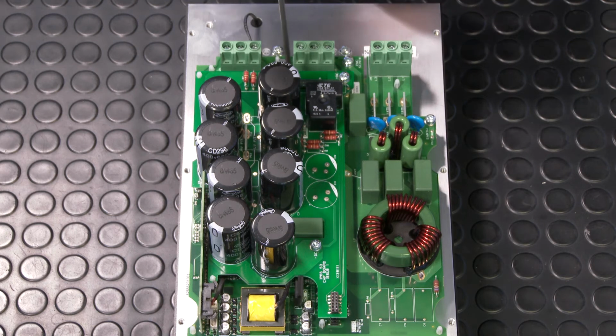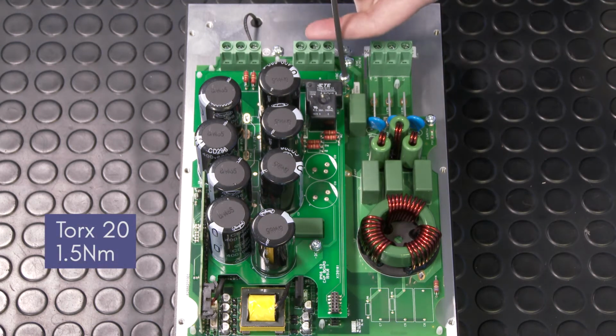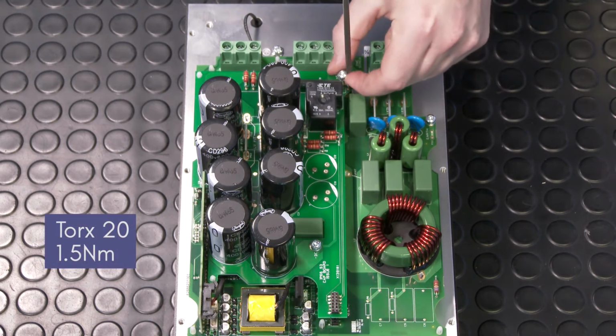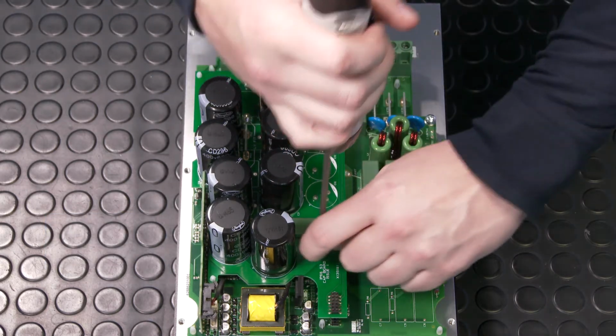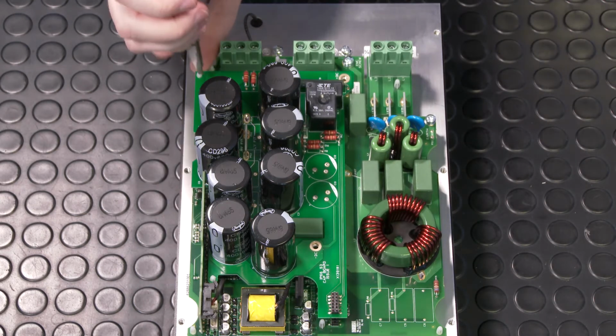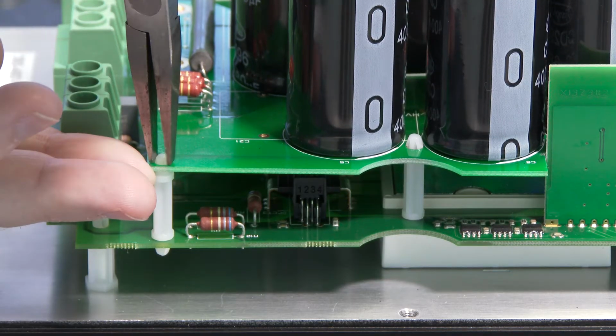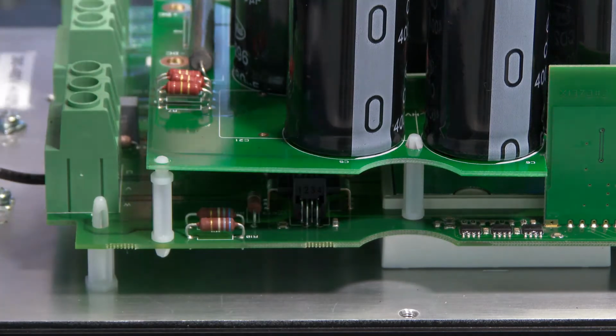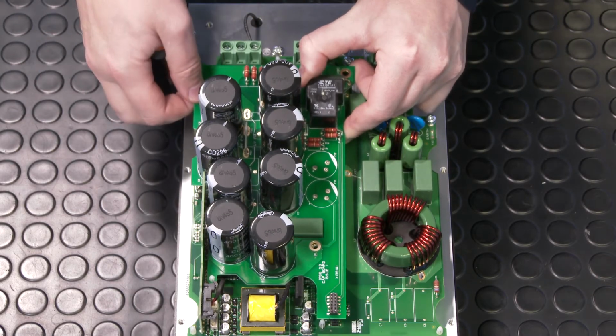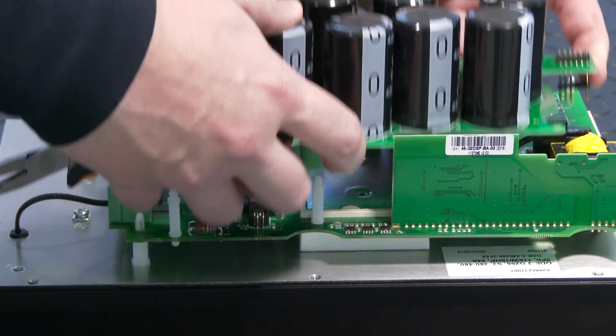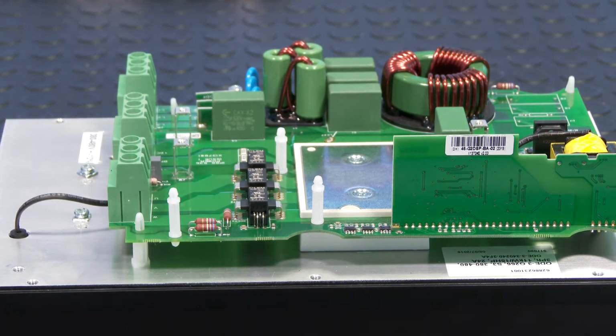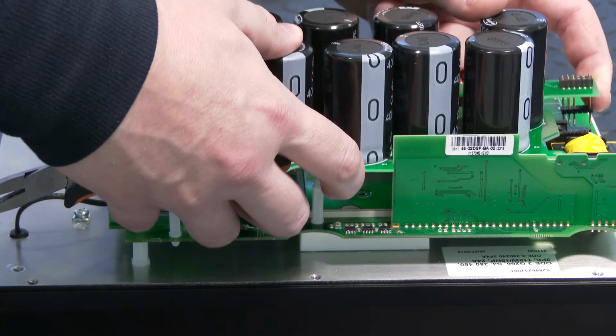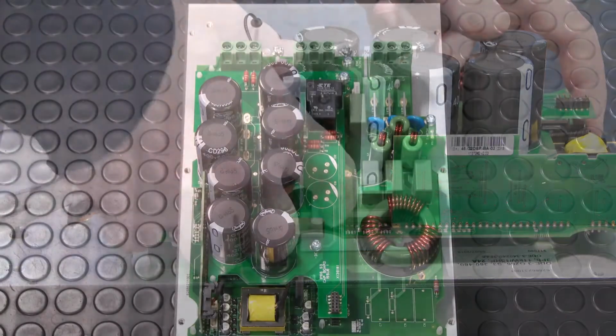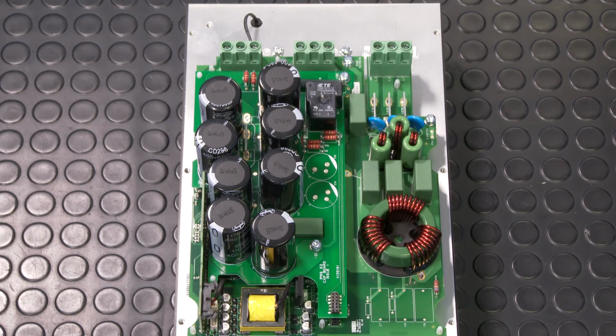To remove the DC capacitor board, use a Torx 20 screwdriver to remove the 3 screws. The torque setting is 1.5 Nm. Using long nose pliers, unclip the 4 plastic pillars from the PCB and lift it away. If your drive doesn't have a heatsink cooling fan, replace the DC capacitor board using the parts supplied in the Preventive maintenance kit and rebuild the drive by reversing the previous steps taken.